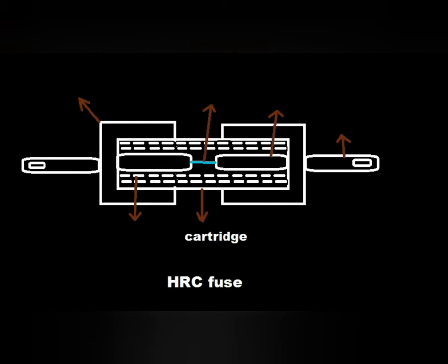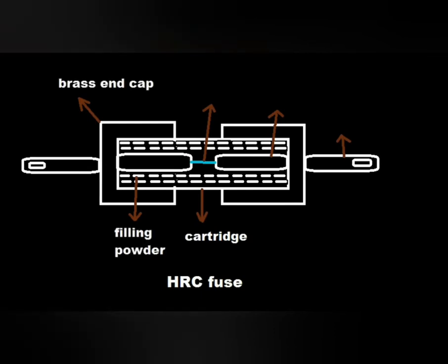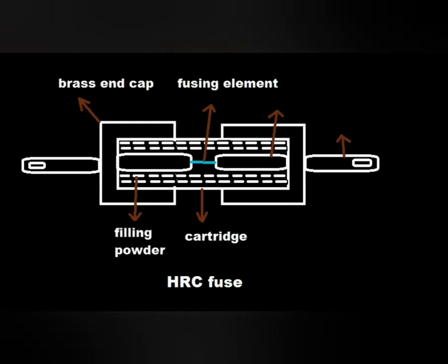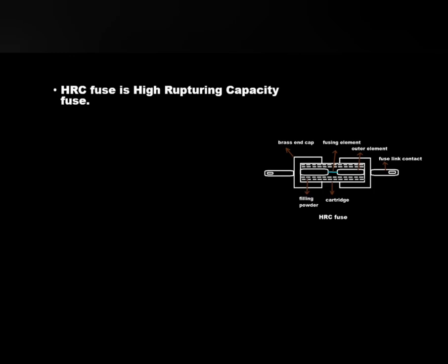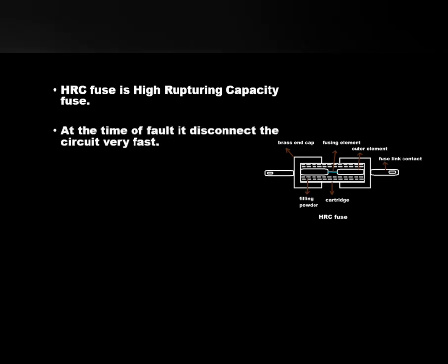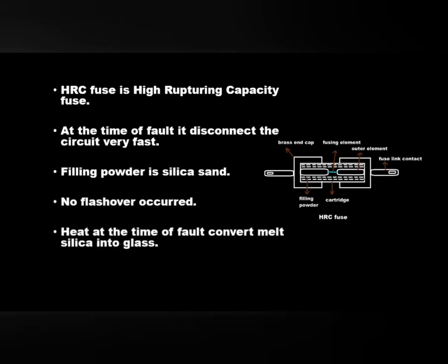HRC fuse is high rupturing capacity fuse. At the time of fault it disconnects the circuit very fast. Filling powder is silica sand. No flashover occurred. Heat at the time of fault converts melt silica into glass.